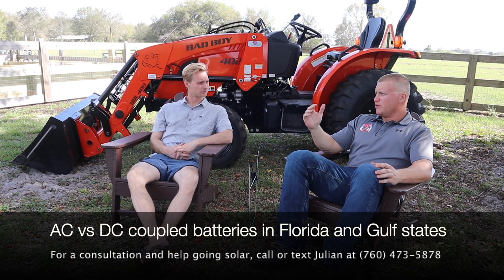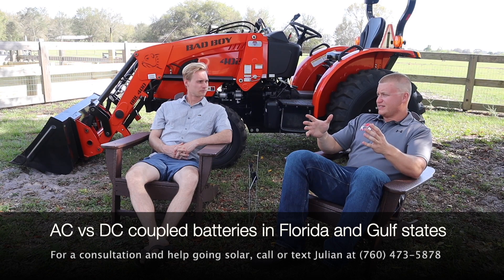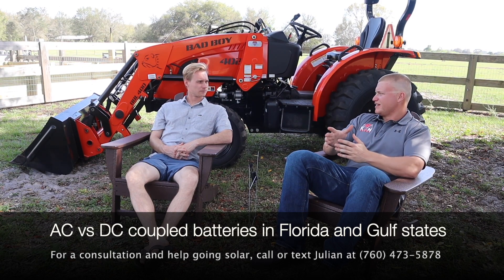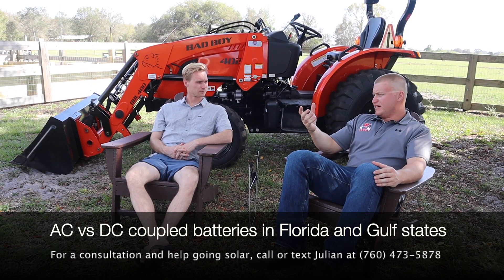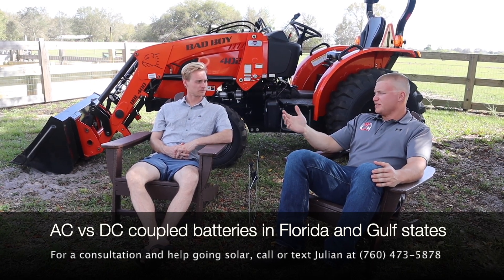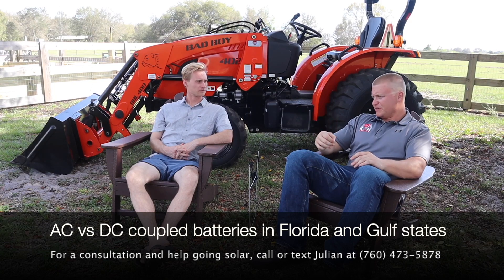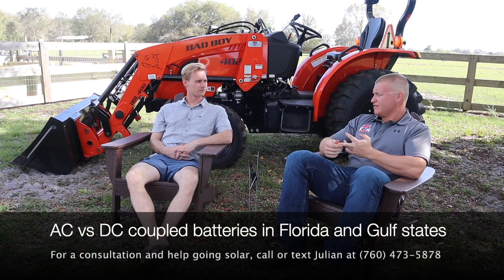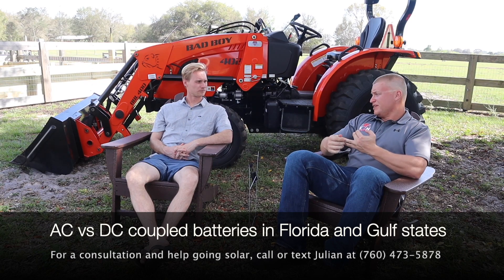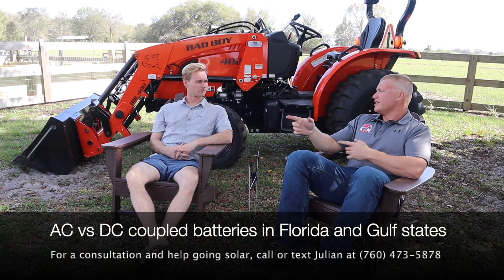If you want to switch over to a DC-coupled battery, the energy hub in the case of SolarEdge is basically directing traffic — it's directing electrons. The energy is produced on the roof again, still in DC. All the solar panels produce in DC, and it goes through an optimizer — that's keeping it in DC, just adjusting the voltage — and it's coming down to that energy hub. There a decision is made: if you need to use it, it's converted, with actually only about a 1% efficiency loss. If you're going to export it, it's converted to AC. But if you're going to store it, it stays in DC and goes directly into the battery — no conversion.